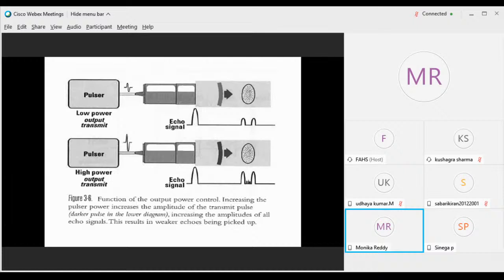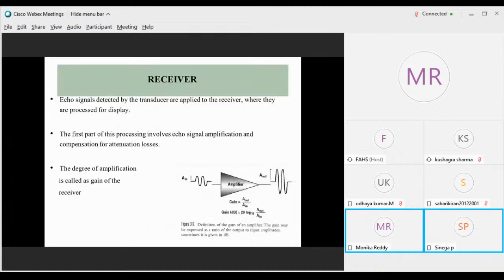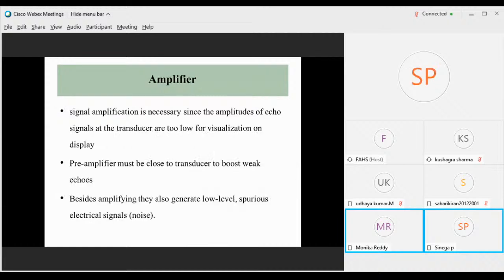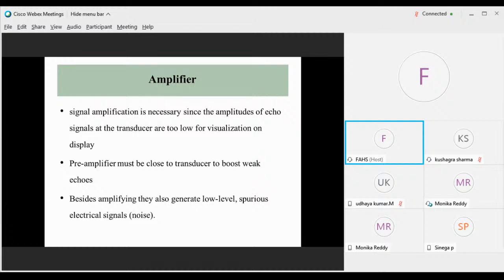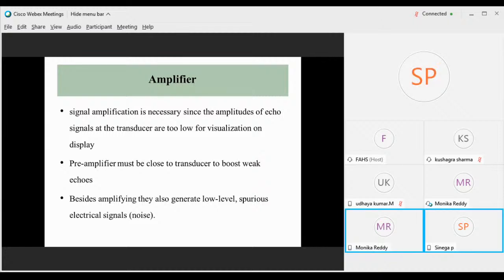So then the receiver: echo signals detected by the transducer are applied to the receiver, where they are processed for display. The first part of this processing involves echo signal amplification and compensation for attenuation losses. So signal amplification and compensation will happen in this receiver, and the degree of amplification is known as the gain of the receiver. Amplifier: this will amplify the signal to provide proper echoes. Besides amplifying, this amplifier will also provide low level spurious electrical signals, which will eventually cause noise in the image formation.